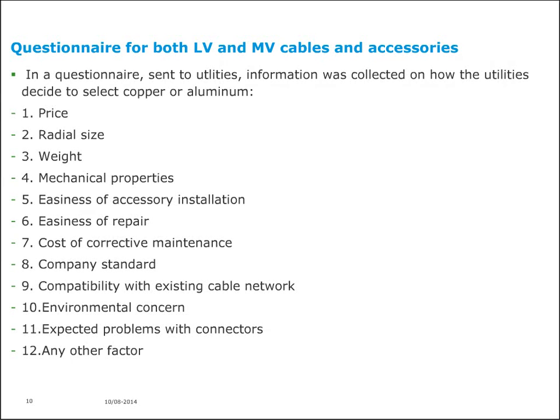Well, let's look to these 12 factors. First, the price. It's obvious that the price plays a part, and I will discuss that later with you. The price is for aluminum lower than copper, and for many utilities this is a major argument to select aluminum. The radial size. I showed you already that copper cables usually have a smaller radius than aluminum, which can be an advantage, for instance, when you install them in ducts.